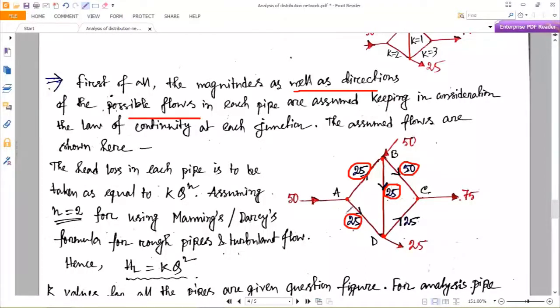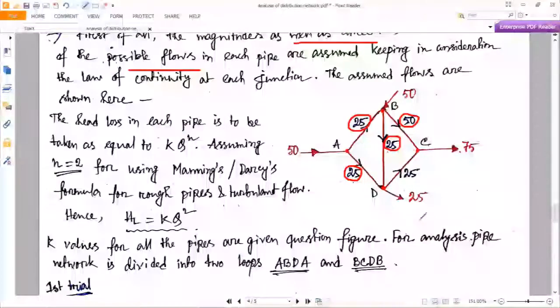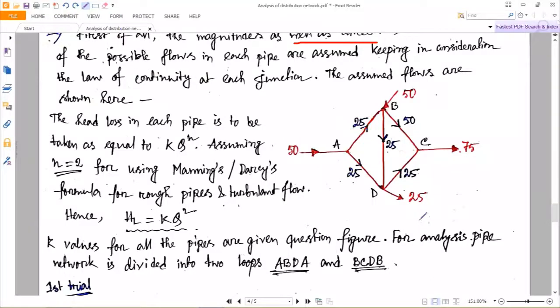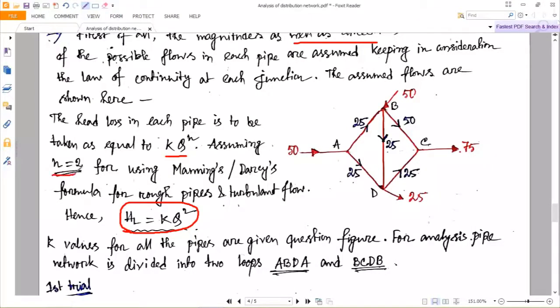The head loss is given as h_L = k × Q^n. We can write h_L = k × Q^2, where n = 2, because we can use Manning's formula or the Darcy-Weisbach formula for head loss calculation. h_L = k × Q^2 is taken, and k values are all given. We have to calculate the h_L value assuming the flow through each pipe. For the first trial we have two loops: loop ABDA and loop BCDB.